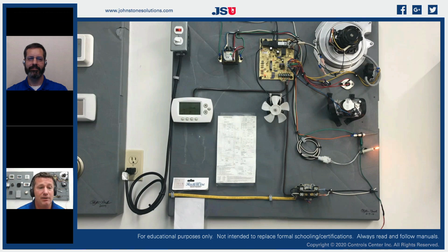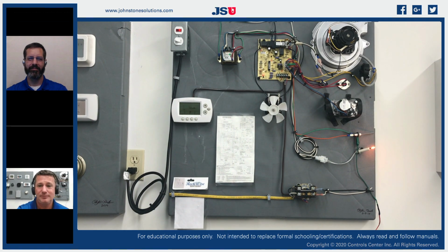Or if we're out in the field and we want to verify the actual trip point of a control board, we can set that. Most of them trip at about 1 microamp typically, but they're all over the place depending on the manufacturer. I've seen them go down as low as 0.17 on some of these commercial applications. So all I'm going to show is that I don't need flame anymore to hold my control circuit. I need flame rectification, or AC to DC voltage with a load on my flame. So the resistors will be the load, the diode will be the rectification circuit converting my AC to DC, and with knowing those specific values, it just takes a little bit of math calculations and it can be found. It took me about 2 weeks or so. It took a little time to plug numbers in, but it worked.